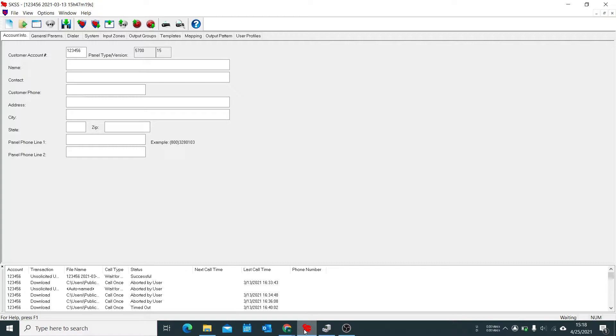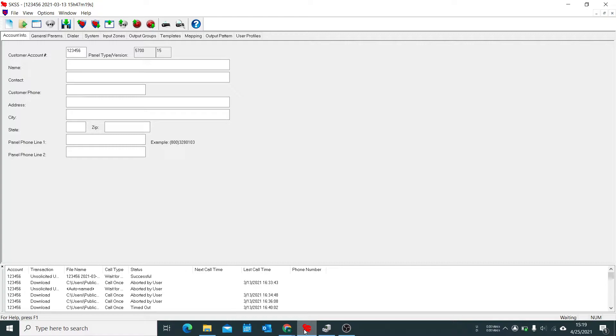That sounds confusing but what it basically means is that you have your SLC in and out on the sounder base itself and then you have a pigtail from the sounder base going to a smoke detector or heat detector. Now whatever point that smoke detector is set to is the point which that sounder base will then be tied to, and it does that to save space and also make programming a little bit easier.